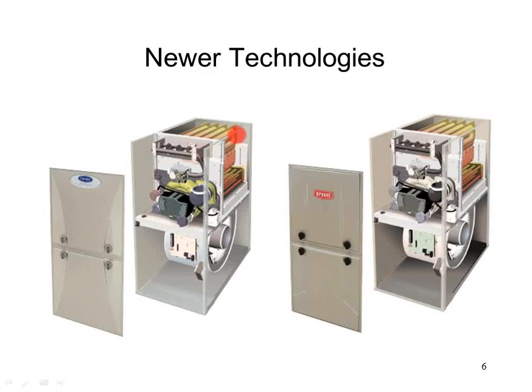But this is your primary heat exchanger here, right? And here's your combustion burners. So the gas is flowing through your gas valve up through your burners. This is a 1, 2, 3, 4 cell system. So we got 4 different burners, so it's a reasonably high BTU unit. Gas flows to the primary heat exchanger, and then it works its way down through the secondary heat exchanger, which are these tubes down here, to get more heat transfer capability. And we'll go through those in a little more detail.